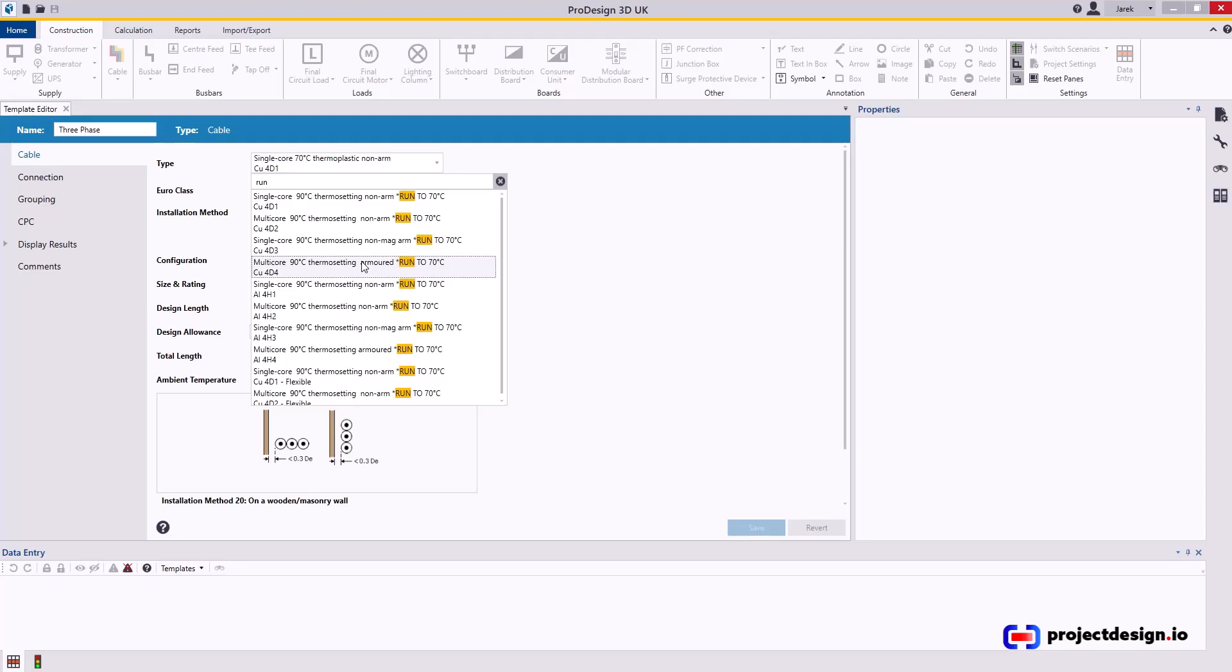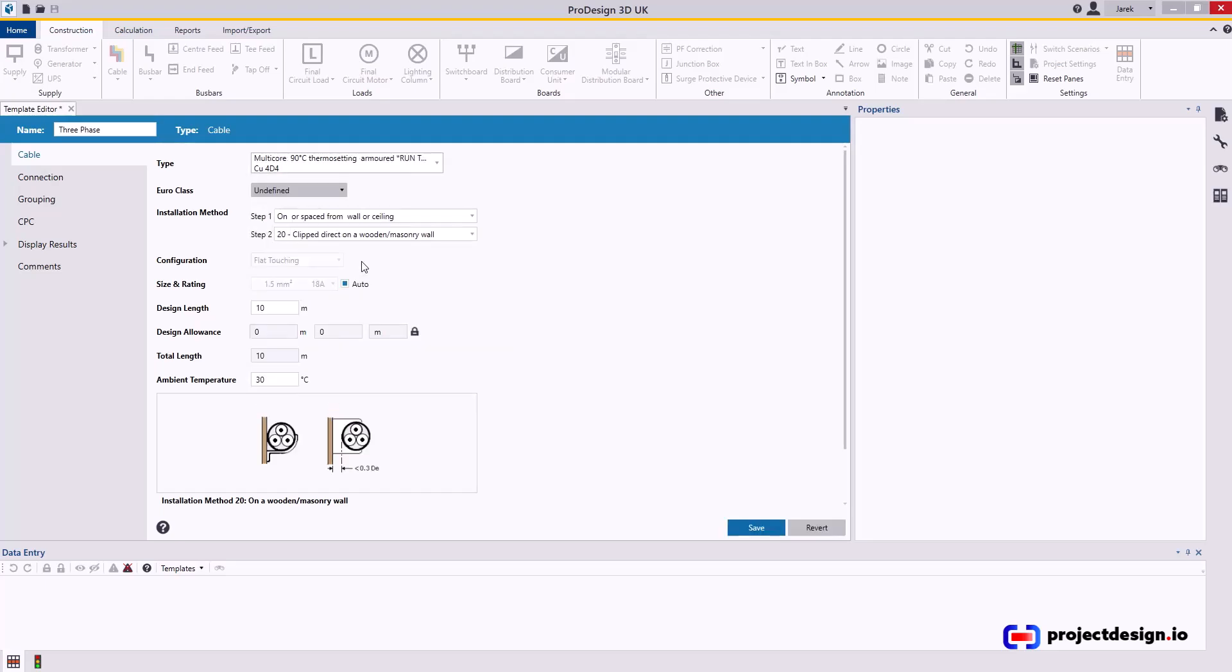But because I can't prove that the cable is connected to switchgear which is also rated 90 degree, then I have to de-rate the cable. So basically it ends up having the same current capacity as normal PVC 70 degree cable. So that's what you do. This is the cable I'm typically using.